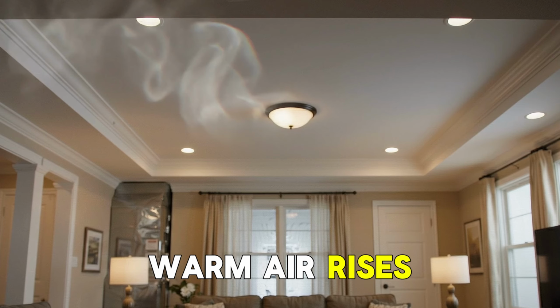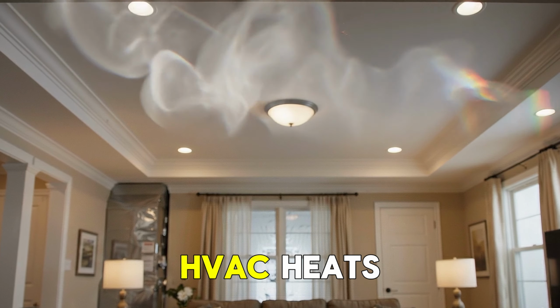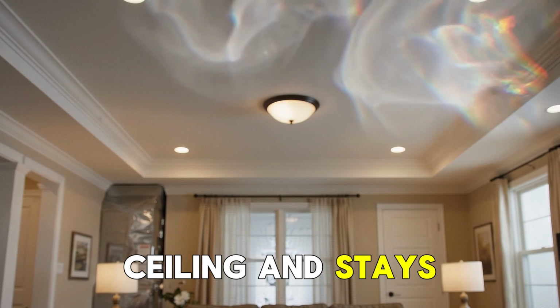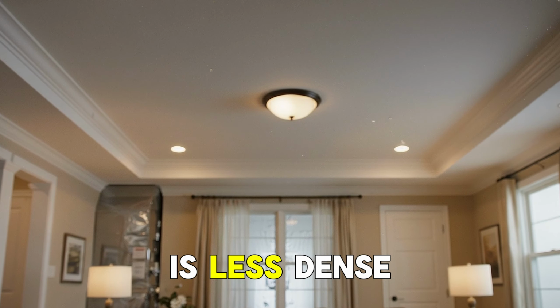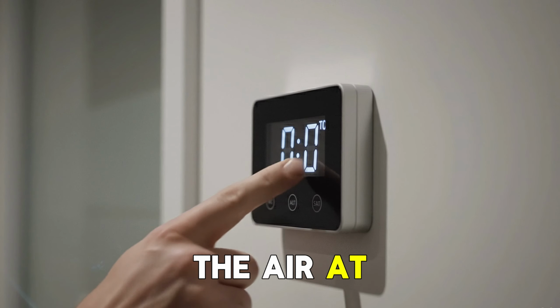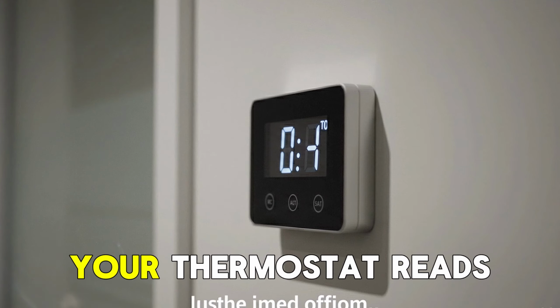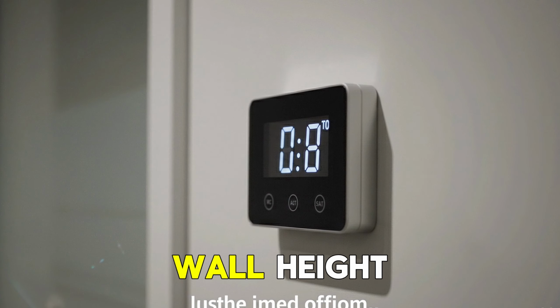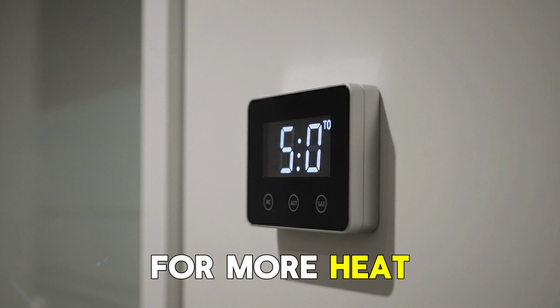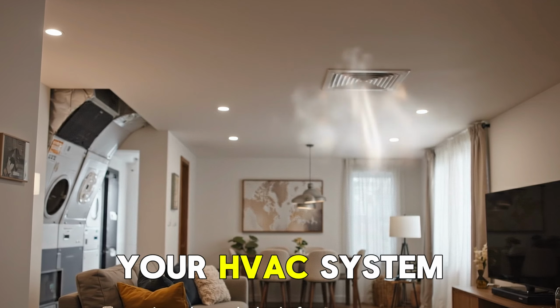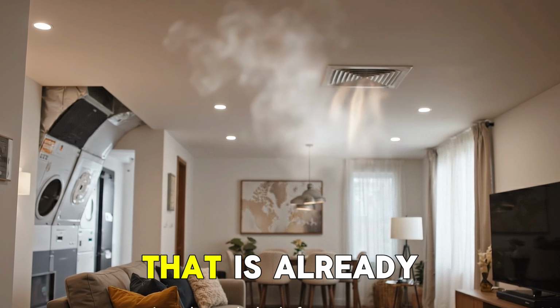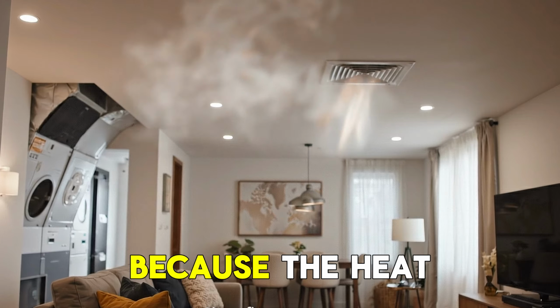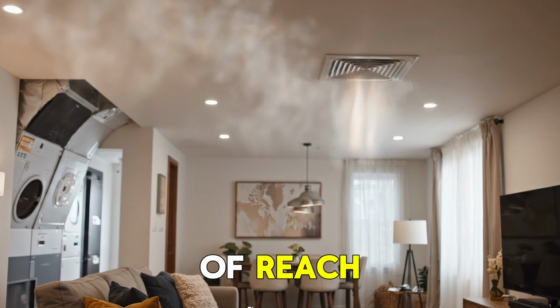Warm air rises. The air your HVAC heats rises to the ceiling and stays there because warm air is less dense. The air at floor level stays cooler. Your thermostat reads the temperature at wall height, so it calls for more heat. Your HVAC system is reheating air that is already in the room because the heat is stratified out of reach.